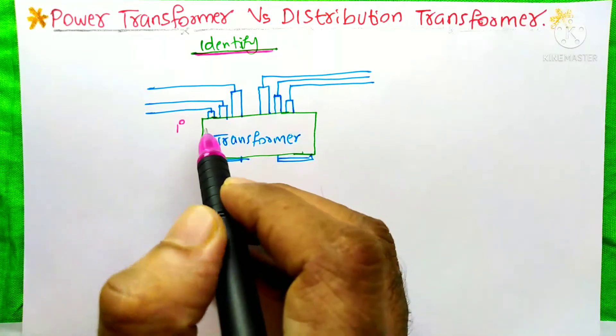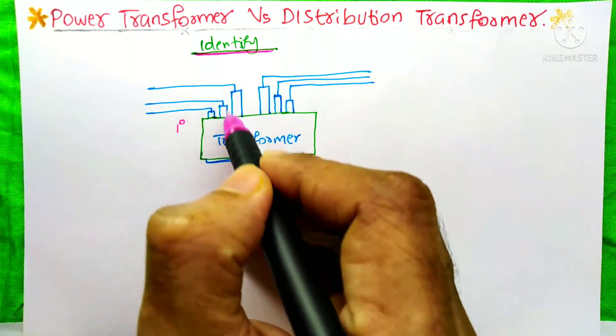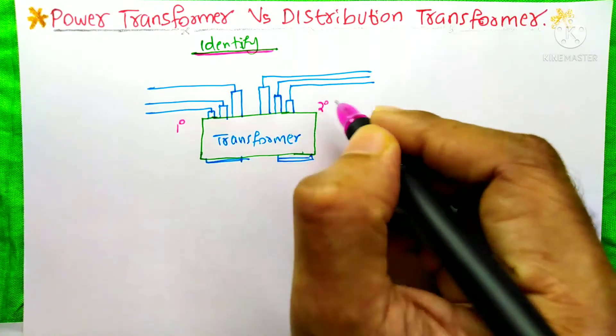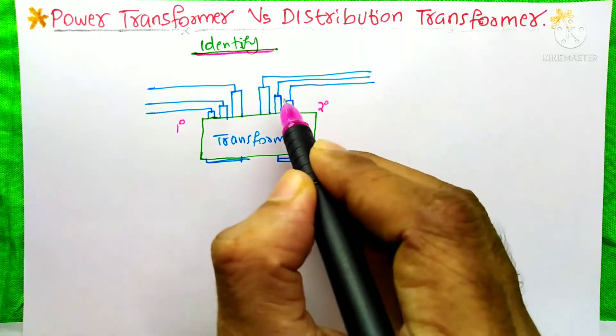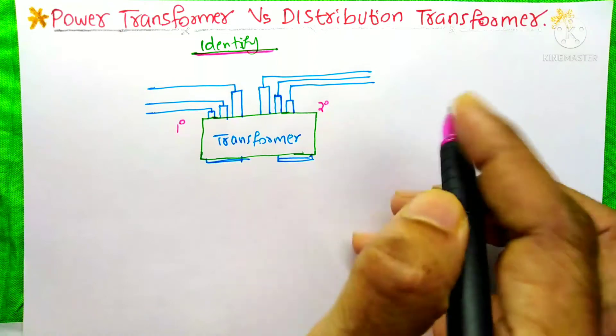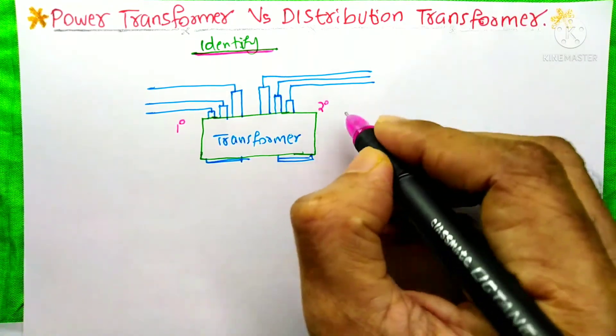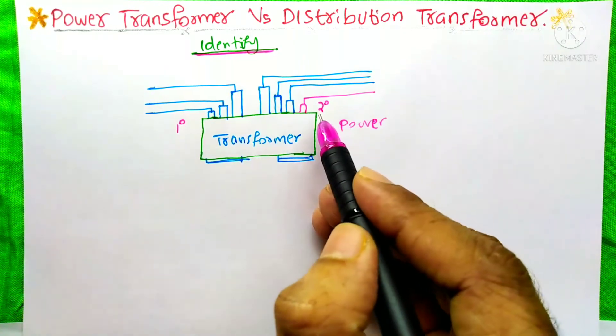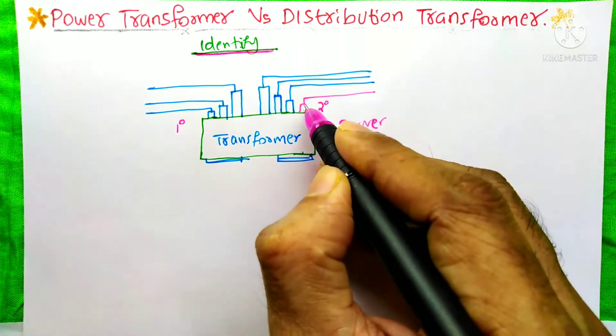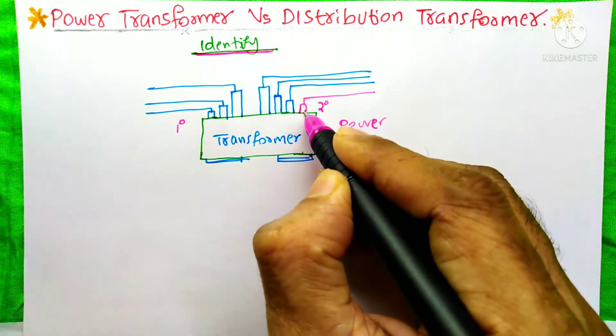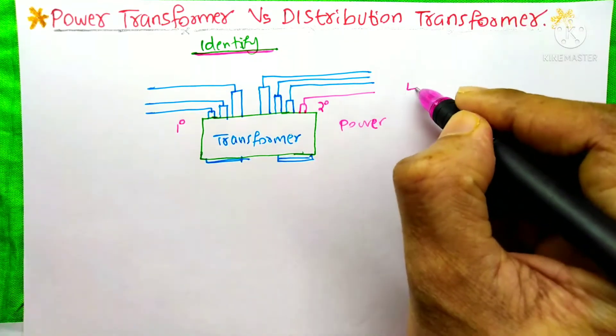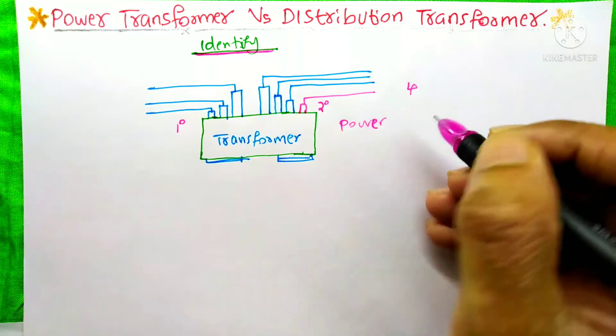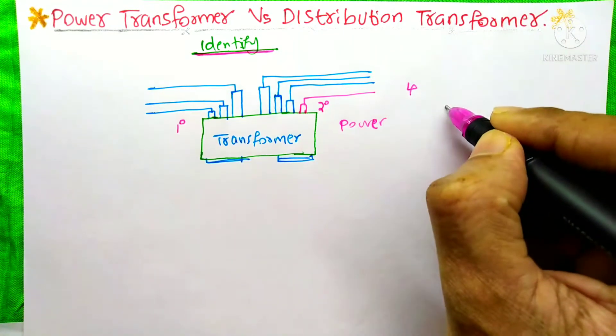If on the primary side of the transformer three conductors are connected to the bushings, and on the secondary side another three conductors are going outside, then we could easily say that it is a power transformer. And if on the secondary side one more conductor is coming out of a bushing — meaning four wires are coming out — then we can say that it is the distribution transformer.